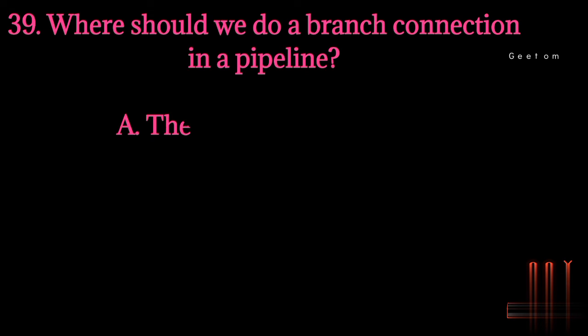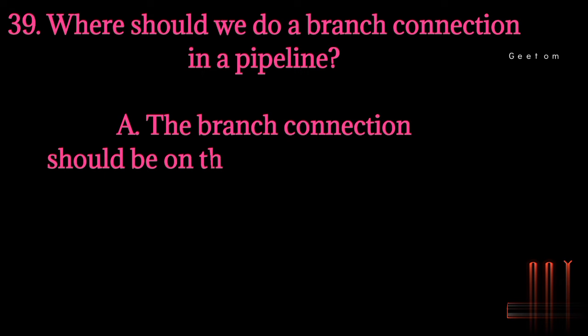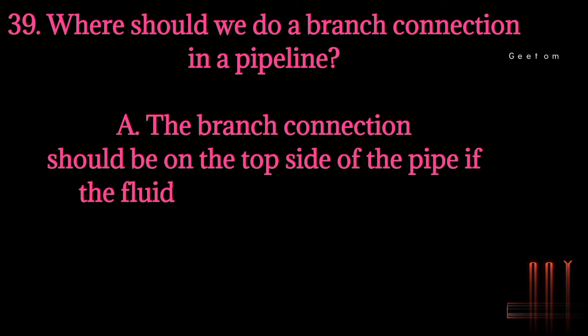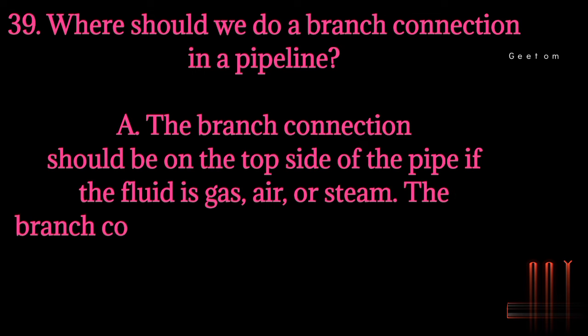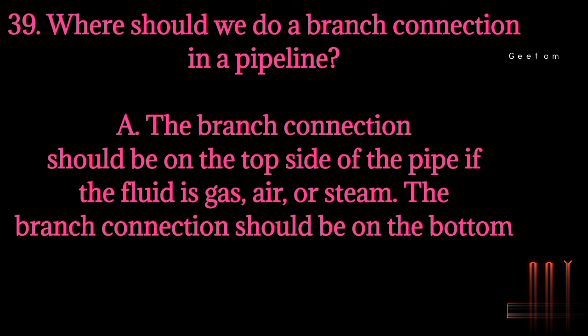Question 39: Where should we do a branch connection in a pipeline? Answer: The branch connection should be on the top side of the pipe if the fluid is gas, air, or steam. The branch connection should be on the bottom side of the pipe if the fluid is liquid.